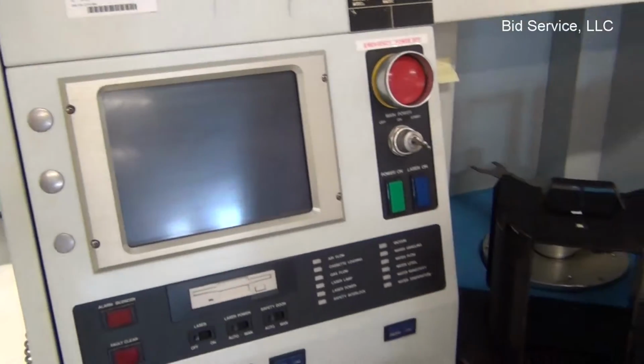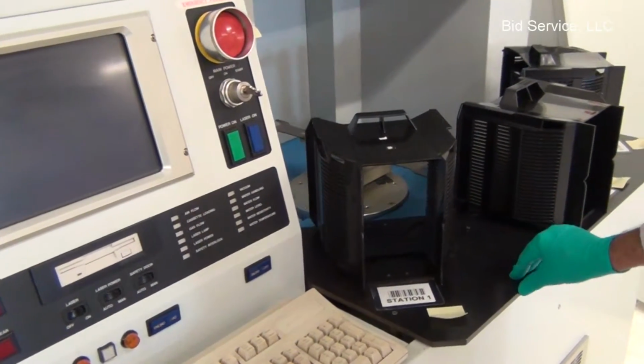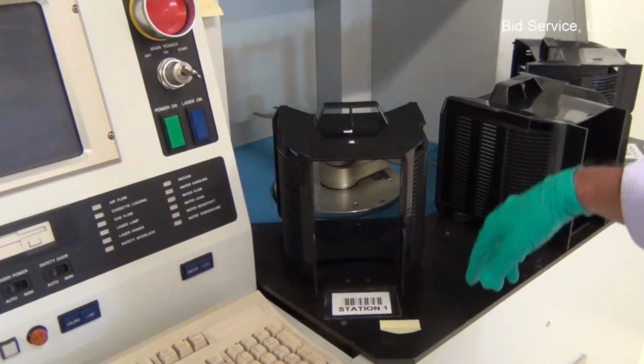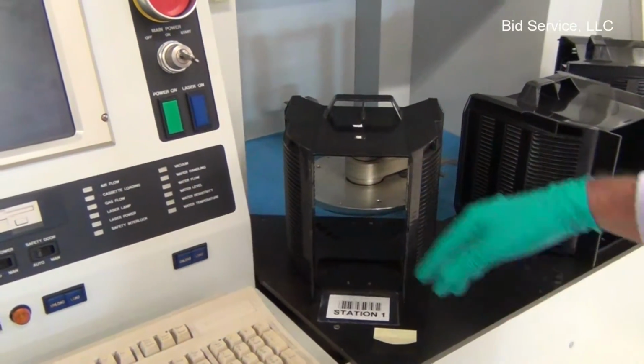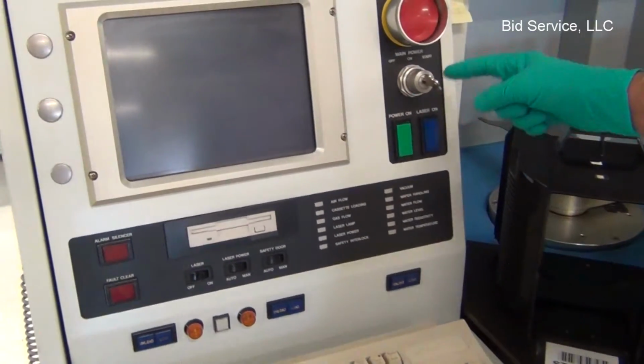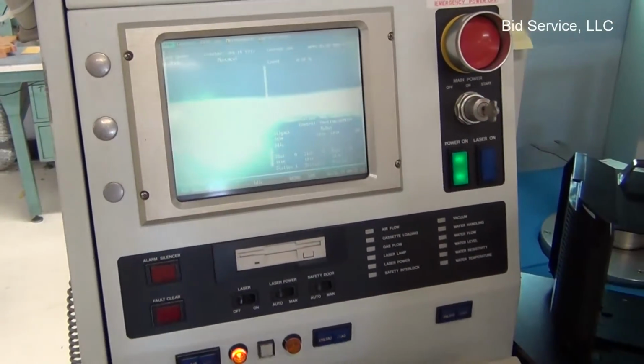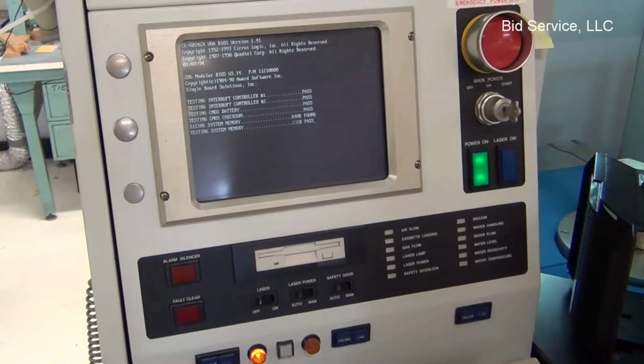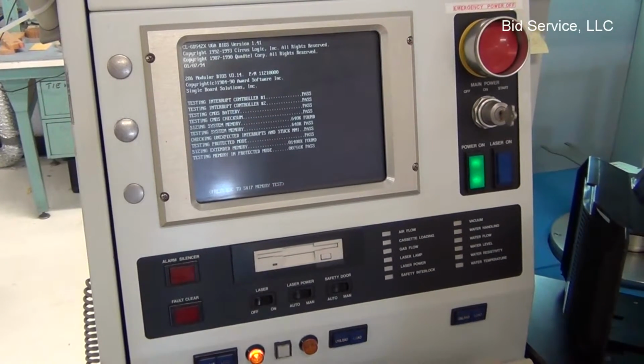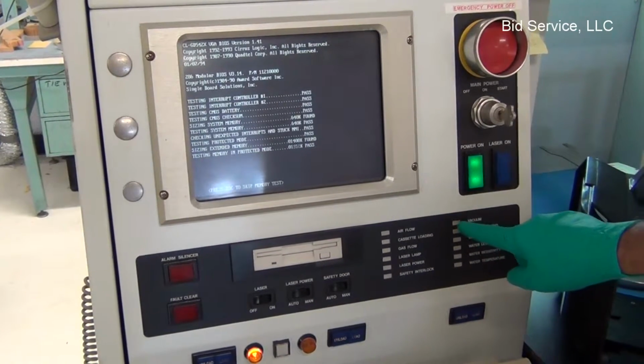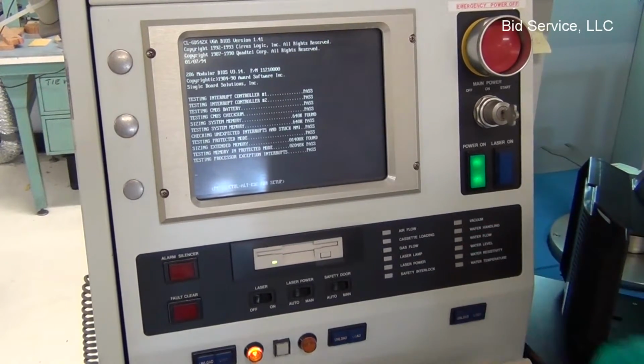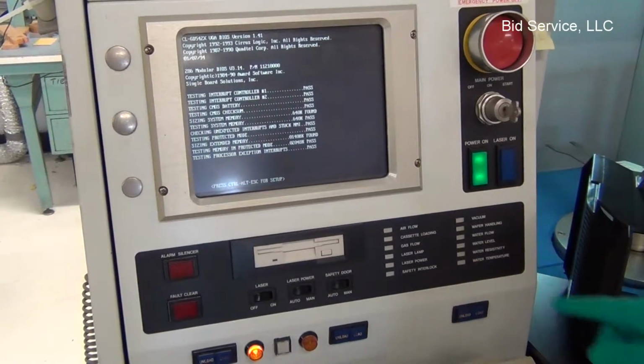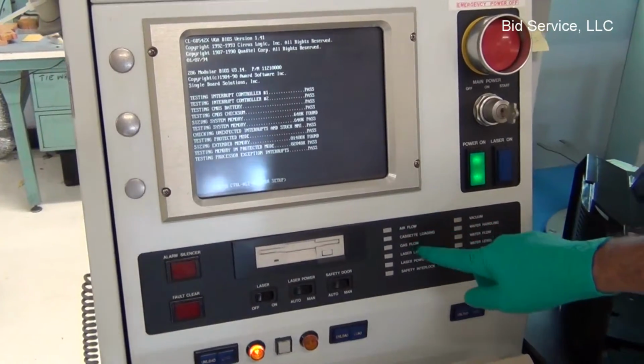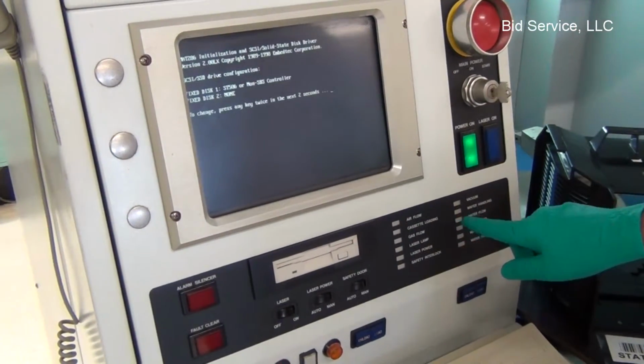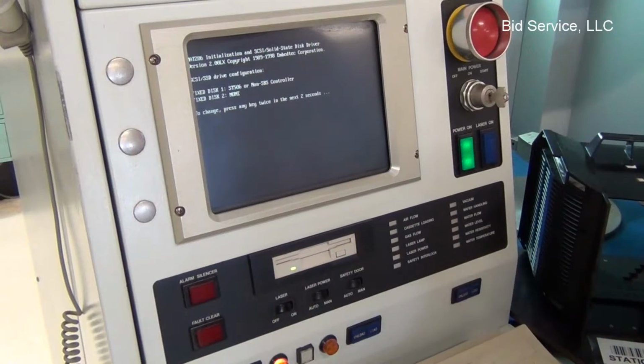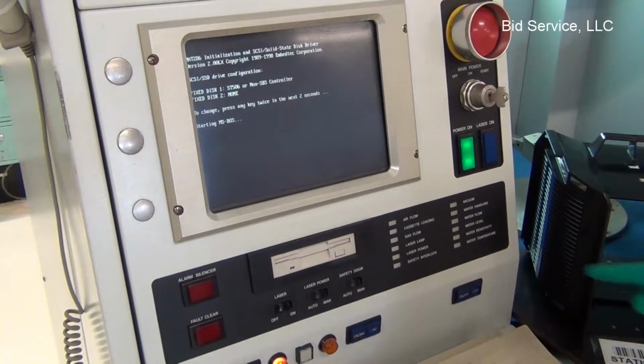Right now the system facilities are hooked up. I have turned on the vacuum pumps and the chiller water for the heat exchanger. And to turn on the system, you have to use this key switch. So if the vacuum is not turned on, this indication will show that the vacuum is not on. And in case the airflow is not there, it will indicate, and also it will indicate the other water flow alarms and water level alarms, because there is a level sensor in the water reservoir.